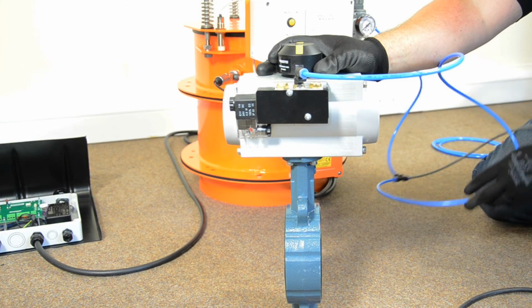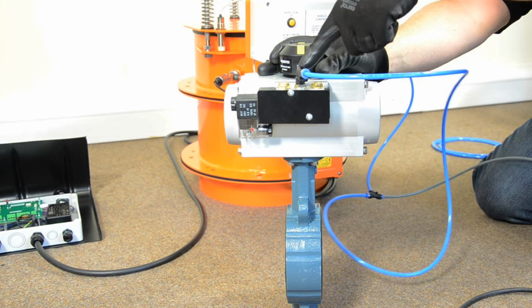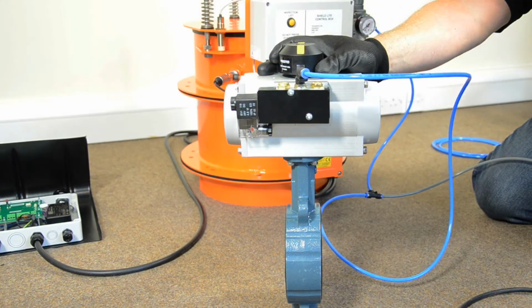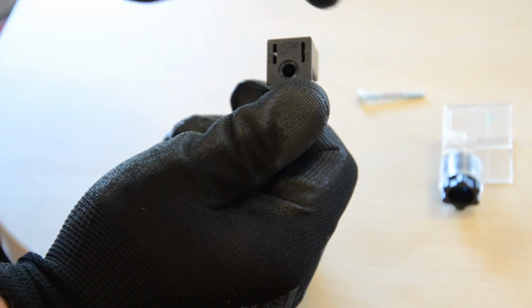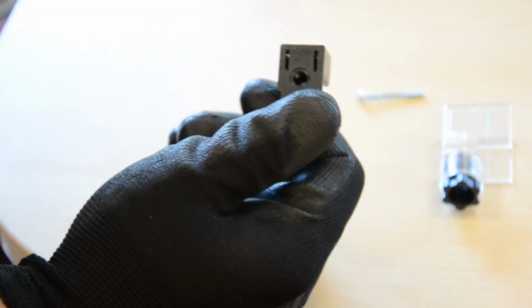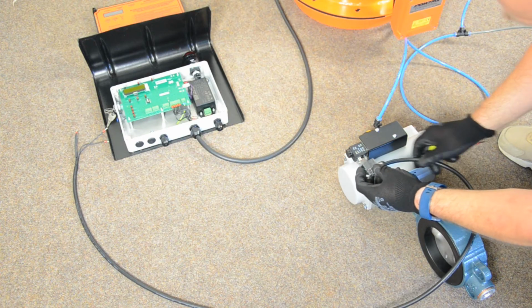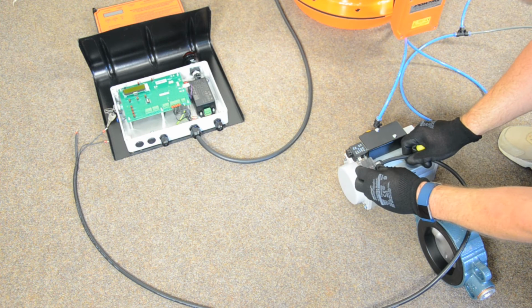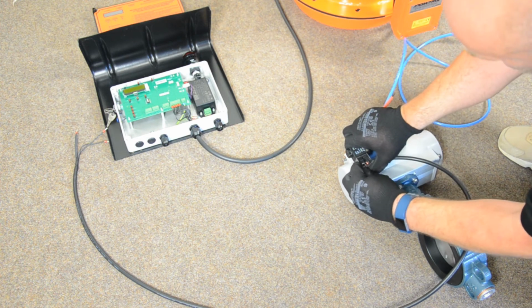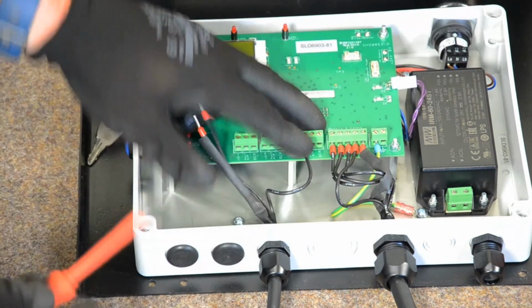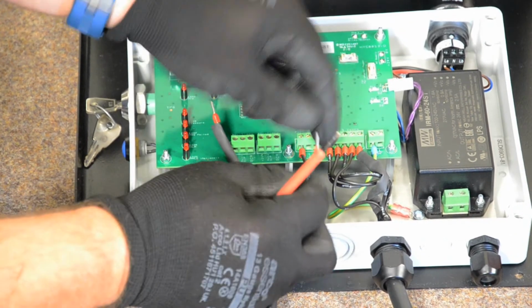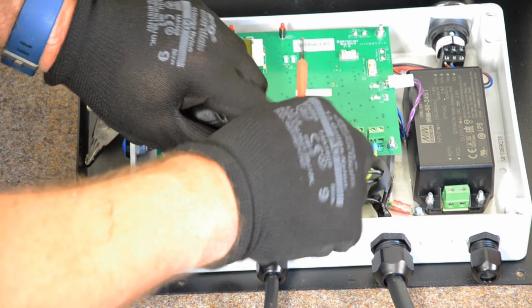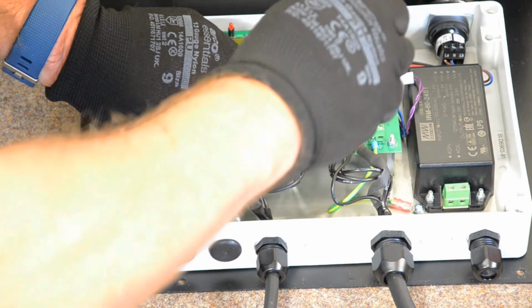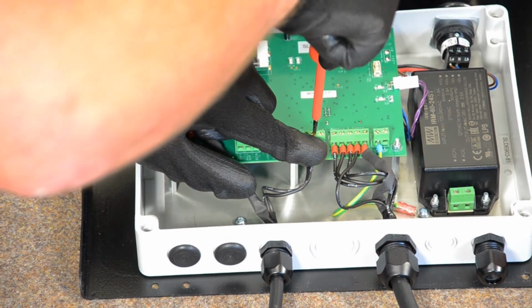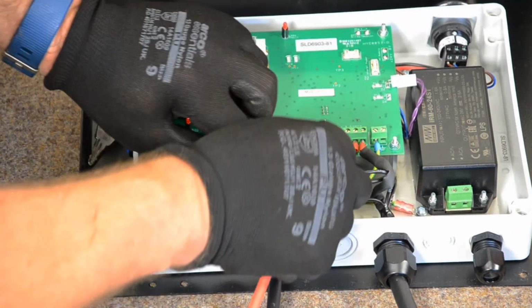Install the normally closed butterfly valve at the fill point and connect the airline as shown. Wire the DIN plug for the inlet valve as numbered 1 and 2. The screen cable does not need to be connected at this end. Connect the DIN plug to the valve. Connect the cables to the panel through the right-hand port and wire it to TB5. 1 is 24 volts, 2 is 0 volts, and 3 is the screen. Again, this is only connected at this end.